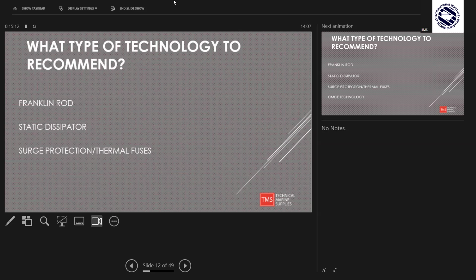You've got surge protection and thermal fuses. If a device ever has anything like this, it probably means it's not working properly, because at the end of the day a true lightning protection or prevention device means you don't need anything like this. There are systems out there on the marketplace that are fundamentally designed for buildings, so once you get over a 3-degree heel, they potentially expose a target area for the lightning to strike on the vessel. These have been used on land for some time, but some companies have been trying to use them at sea, and there have been issues. Hence why they generally protect themselves with surge protection and thermal fuses as well. So that's something else to keep an eye on or look out for.